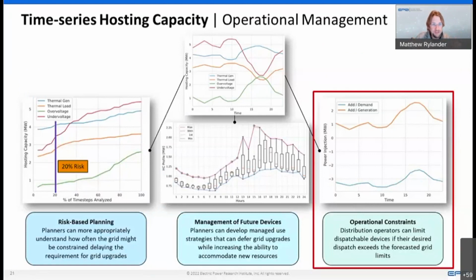As this whole session is focused on active management of DER, these time-series hosting capacity curves are also being used in new ways today to provide dynamic operating envelopes—giving us the perspective that a day ahead we might need to actively manage devices to operate within a particular window. This is highlighted in the right-hand figure of this slide: you can create an envelope of what the radial network or feeder can currently accommodate, both from a generation and a demand aspect. As long as controllable devices operate within this envelope, the grid can avoid any potential violations during that window of time.